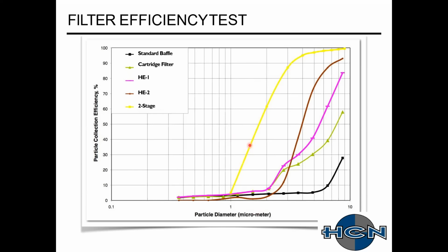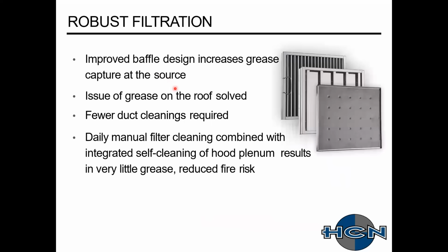Biggest thing with this is, if you're getting a better filter, you also have to account for the static pressure loss that you're going to have with that fan. So improving that capture at the hood is going to resolve a lot of the grease problems that you have in your hood and your duct.